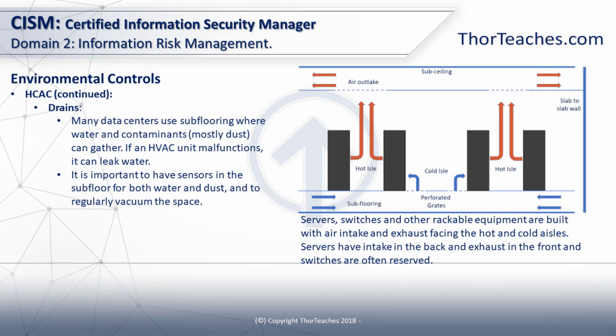On the graphic here, you can see the sub-ceilings and the subfloors we talked about earlier. So the top blue line is the actual ceiling. The bottom blue line is the actual floor. And then remember, the walls we have are slab to slab, so they go from the true ceiling to the true floor. Then we have the raised floor, the subflooring. That's where all the cables are run, and also where that dust was gathered in that data center.